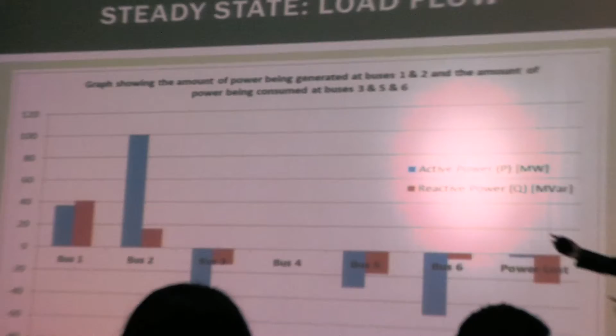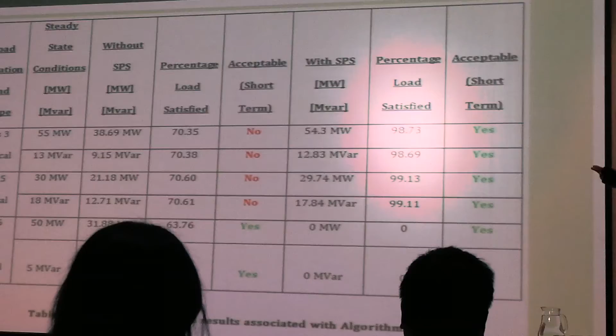However, if the SPS is in operation, by controlled load shedding and the utilisation of capacitor banks, we are able to satisfy 98% of the critical load. That's shown in this table here. Without the SPS in operation, only 70%, but with the SPS, at least 98%.